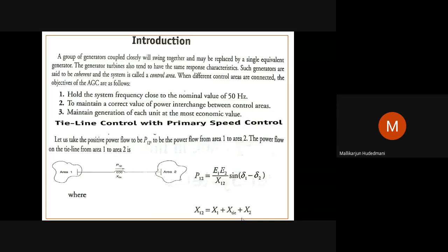Let us expect there is an exchange of power from area 1 to area 2, like power flow from area 1 to 2 is P12. What is the megawatt transferred from 1 to 2? That is given by the expression written at the right. The bus voltage of the transmission section bus at area 1, say E1, with angle delta 1. E1 angle delta 1 are the parameters concerning bus 1 at area 1.